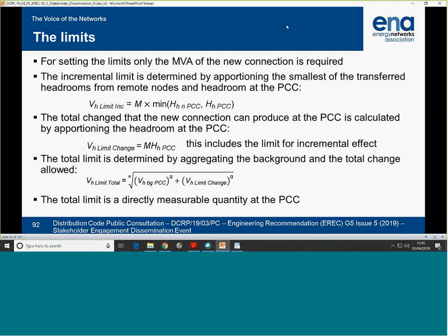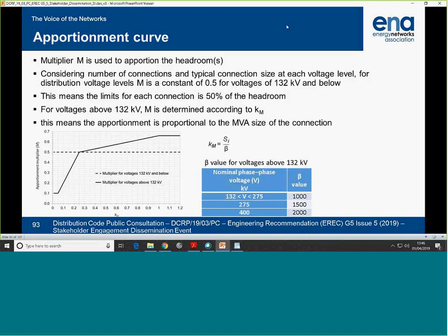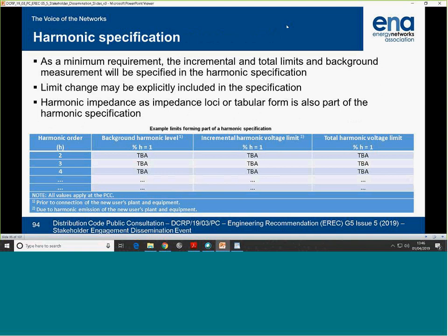Determine the headrooms from measured values and from transfer coefficients. It only depends on the size of the connection. That's all. And the limit. The document is typical. You may choose to add other limits in there. As long as you've got at least these three, you can determine the resonance limit, and you can determine the change limit.